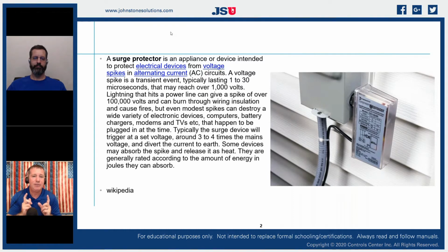A voltage spike is a transient event and typically lasts between 1 and 30 microseconds. It's a very short shift of electrical current, and sometimes it's over 1,000 volts, especially on these 230-volt systems that we see. And when we talk about the lightning aspect, now we're talking about 100,000 volts of electricity, right? So those high voltage surges, as they come through our electrical systems, through our conduits and through our conductors, that's where we introduce them into our electrical circuits that typically are not designed for those types of voltages.